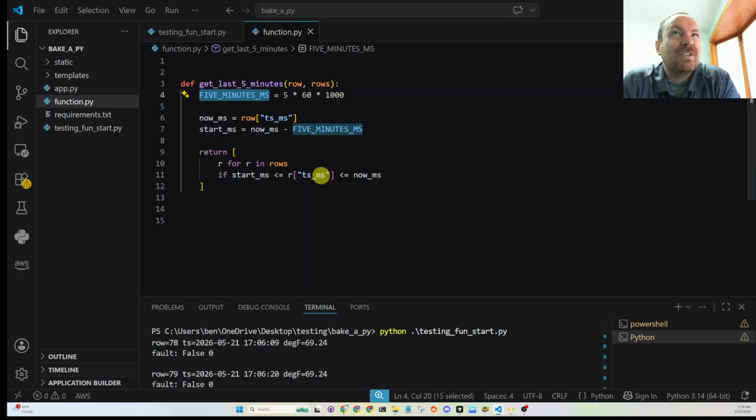I'm not really looking too much into that, and from a mechanical standpoint, I would just evaluate if the sensor is maintaining some kind of bounds. You're thinking a little bit more: if this is a heat exchanger, and you turn the gas burner on, or you open that chilled water or hot water coil or a burner, the manufacturer would have a rate of change they would expect for that air to warm up or that water to cool down.